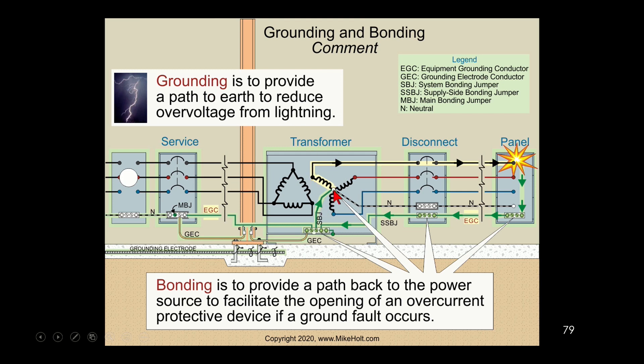That ground connection goes from the system through the system bonding jumper, then we run the grounding electrode conductor and make a connection to the earth — that grounds the secondary winding. It also says bonding: bonding provides a path back to the power source to facilitate the opening of the overcurrent device. The system bonding jumper bonds all those conductors back over to the source, so if we have a proper bond and effective ground fault current path, we can clear the fault.